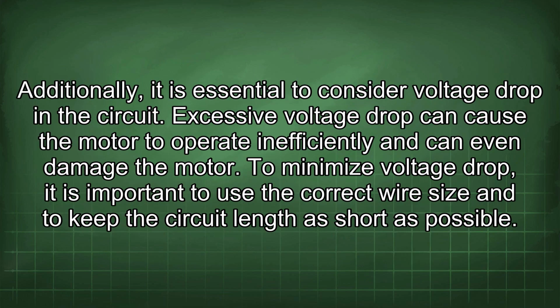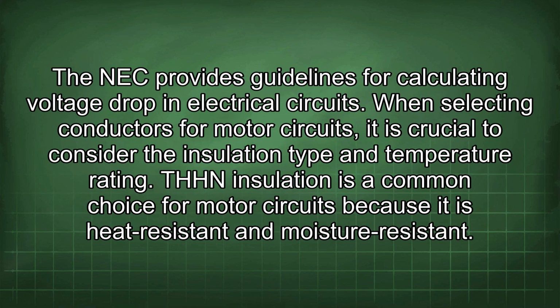Additionally, it is essential to consider voltage drop in the circuit. Excessive voltage drop can cause the motor to operate inefficiently and can even damage the motor. To minimize voltage drop, it is important to use the correct wire size and to keep the circuit length as short as possible. The NEC provides guidelines for calculating voltage drop in electrical circuits.